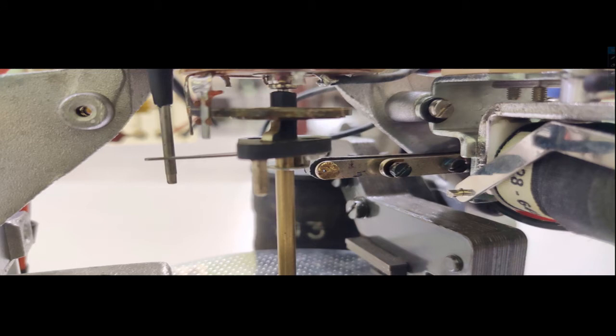You see, this is the normally open switch, which is responsible for closing the tripping coil. So it is normally open. You see two portions are there, one is this one, another is this one, and there is a gap between these two things. So that means this is a normally open switch. When this projected part creates some pressure on that particular area, it will become closed, and the DC power is connected to the tripping coil.